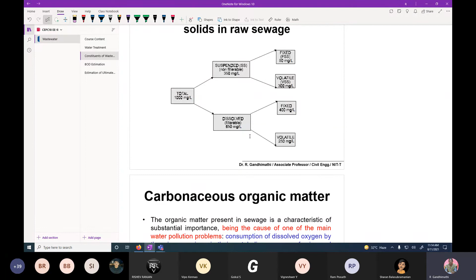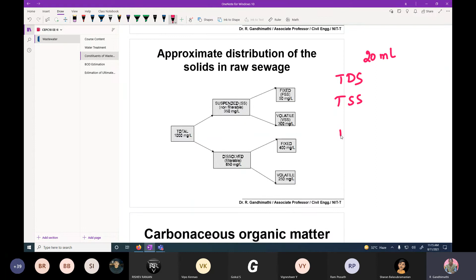We have to take a known volume of the sample, maybe 20 ml of wastewater, and then take the crucible. Here there are 2 different types of crucible. One is the silica crucible. The crucible is made of silica as well as porcelain and other materials. Silica will withstand very high temperature, but a porcelain dish can withstand only up to 105 or 110 degrees. Therefore, you have to be very careful whether you are going to measure only the total dissolved solids or total suspended solids, or whether you are interested in total volatile solids or total fixed solids.